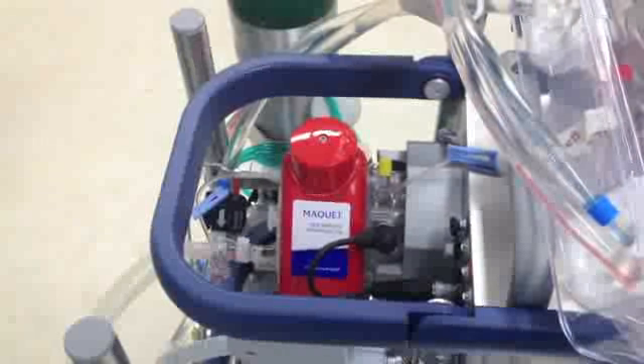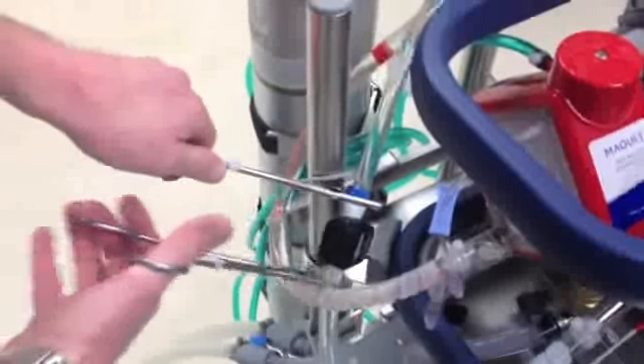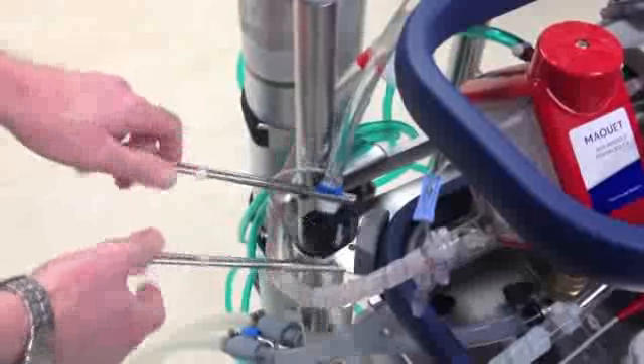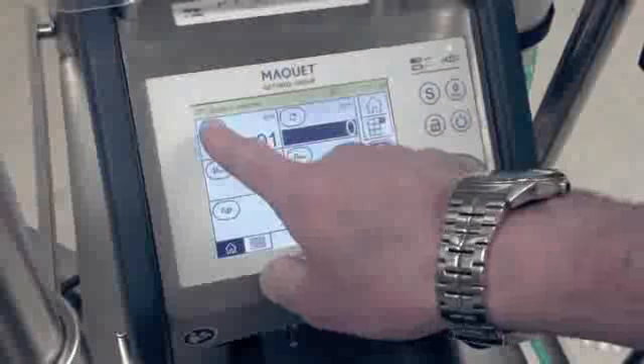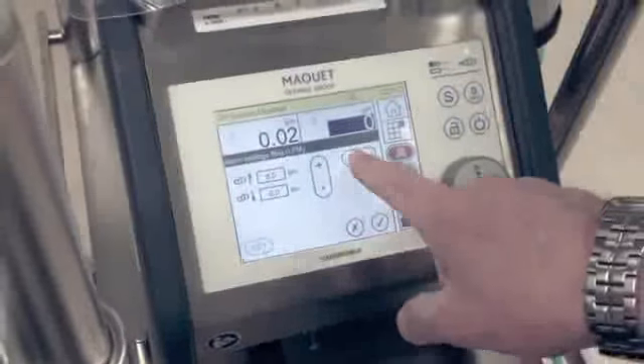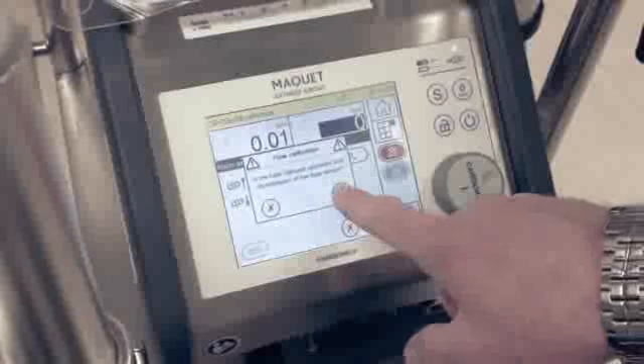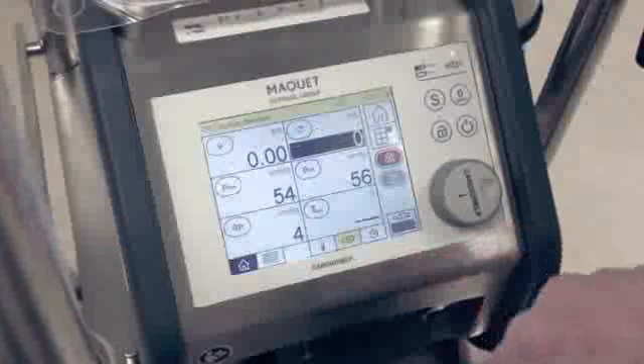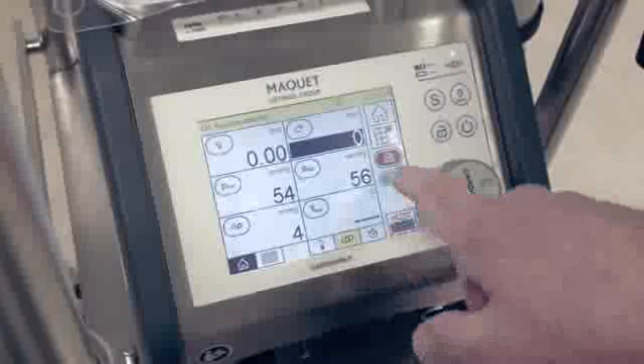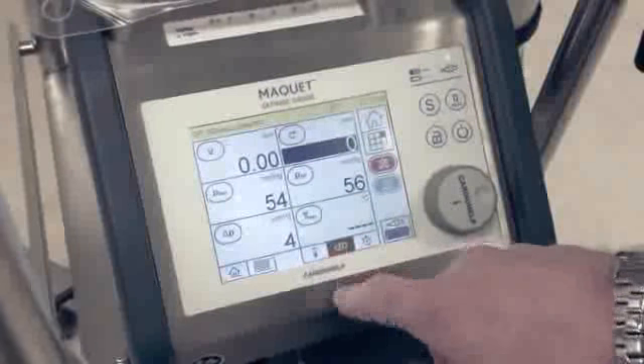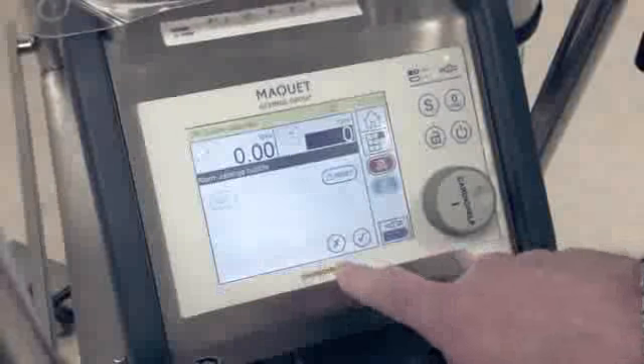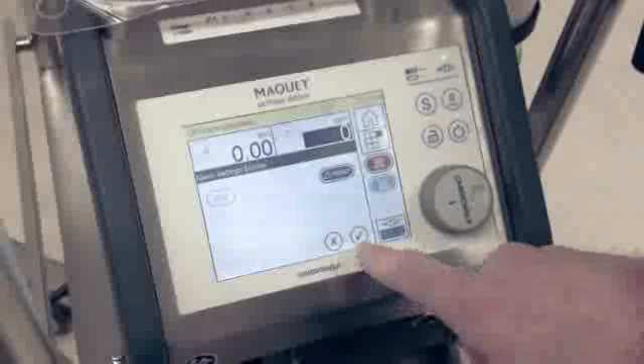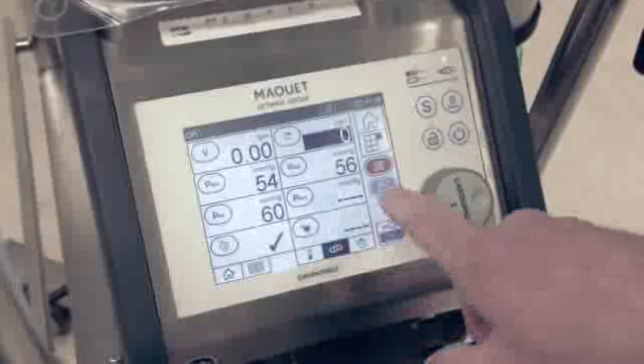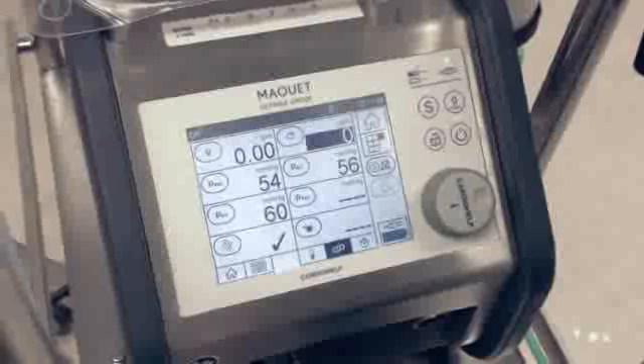And you'll take metal clamps, and you'll clamp on either side of the flow probe so you can zero for the flow. And to do that, there needs to be 0 flow, so you clamp it. You hit the flow button, which is the top left-hand V button. You hit 0, and you hit the green check, and you hit the green check again to confirm it. Then you hit the yellow button down at the bottom right. That's the bubble sensor. You hit the bubble sensor, hit reset, hit the green check, and then you'll turn off global override by just tapping the red button.